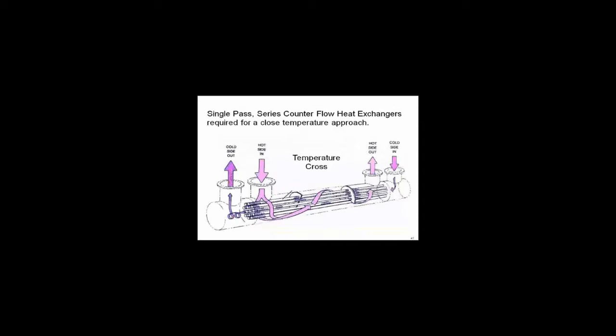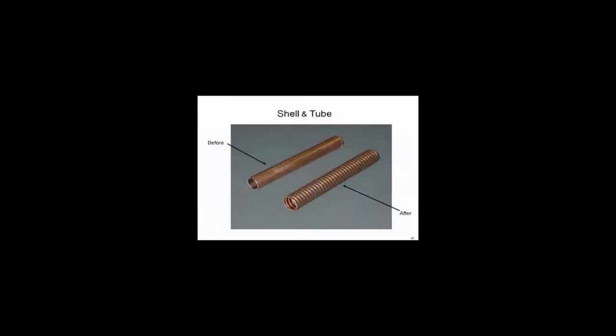But there's another approach available to you on water-side economizers. You can go to single pass series counter flow heat exchangers, and we're going to find in a few minutes what single pass counter flow means for all types of heat exchangers. But in essence, you want the coldest water with the coldest on each side, and you want to make sure that you've got it single pass counter flow. The advantage of these is they're a lot easier to clean.